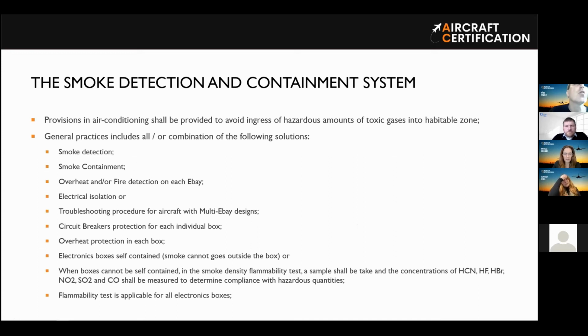The other system that I will talk about is the smoke detection and containment system. This system is responsible for detecting smoke in case of failure in the bay. So let's say that you have an electronic box there that has failed and starts to release smoke. We don't know if this smoke is toxic or not, but it may have a good content of contaminants that can cause a hazard for the occupants. So in this condition, we need to avoid the contamination of occupied zones.